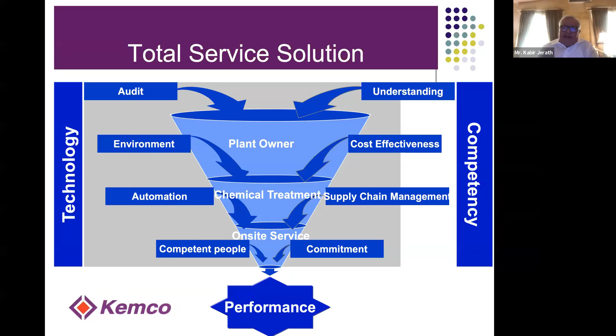This is a given, a non-debatable reality. Because if you don't operate the plant 24 hours through the day, you're allowing the RO plant to be attacked by foulants, allowing it to degrade because of raw water quality. Yes, you do flush with permeate water, but that permeate water is an expensive resource and costly to produce, which is being used merely to flush the membranes. I would encourage everyone to consider designing and operating plants 24 hours a day.